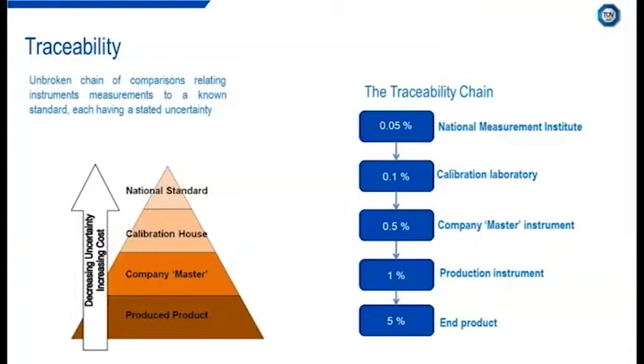The third important term related to fundamentals of measurement that we will cover today is traceability. Traceability refers to an unbroken chain of comparisons relating an instrument's measurements to a known standard, each having a stated uncertainty. Calibration to a traceable standard can be used to determine an instrument's precision and accuracy.